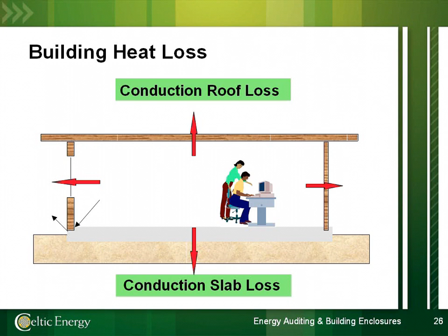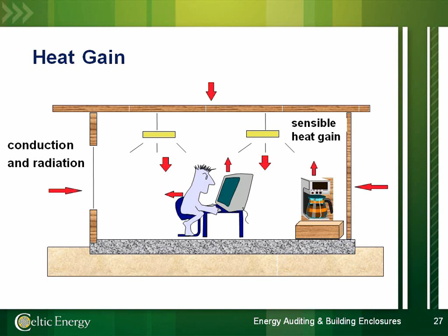In terms of conduction and radiation, we most often feel the direct effect through windows, but on a hot summer day, sun beating on the roof heats that roof assembly, which radiates energy into the occupied space and directly increases the cooling load. Similarly, within our spaces, there are internal gains that contribute to overall heat transfer from lights and appliances to the occupants.